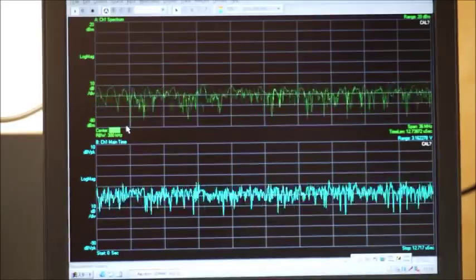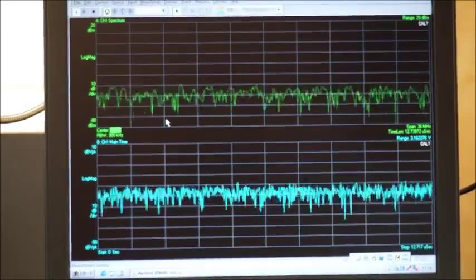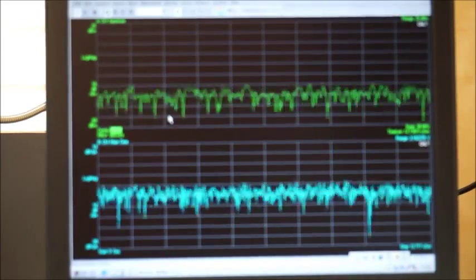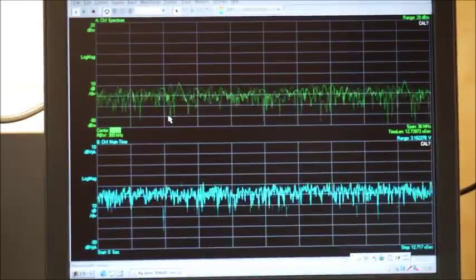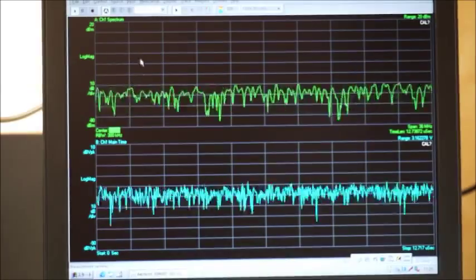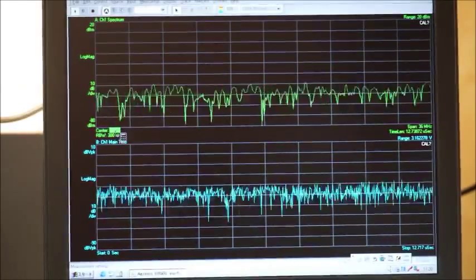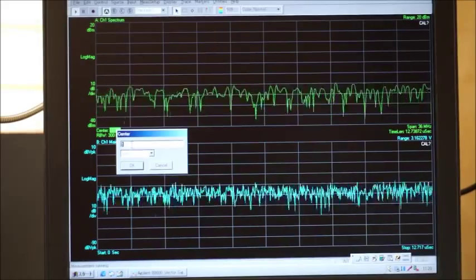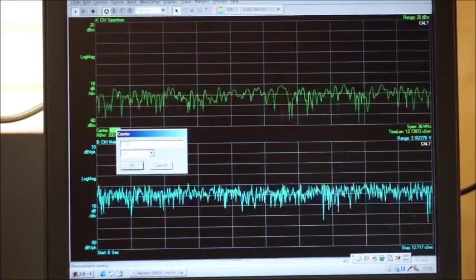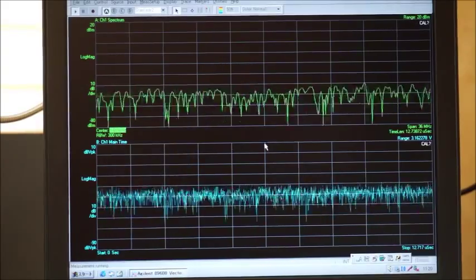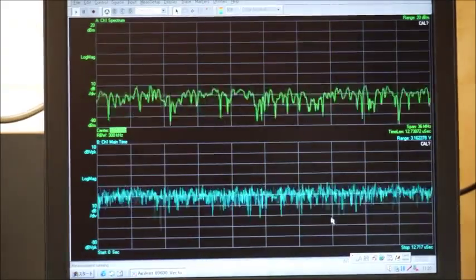I'm inputting the signal from a signal generator at CW carrier on the frequency 1.65 GHz. So I will set up 1.65 GHz for the spectrum analyzer. Now it's set.